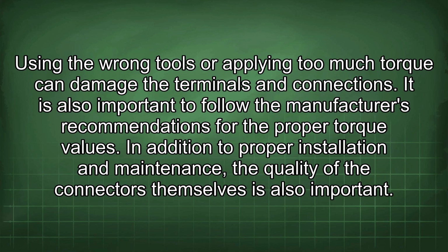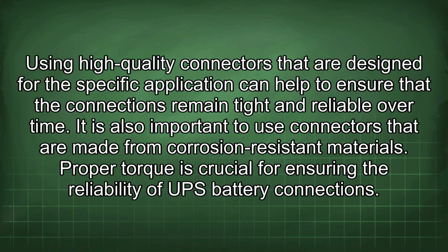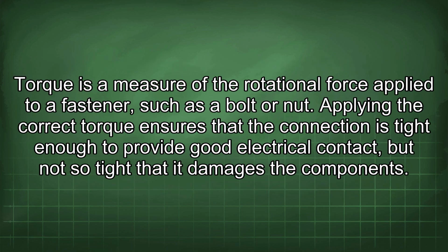In addition to proper installation and maintenance, the quality of the connectors themselves is also important. Using high-quality connectors that are designed for the specific application can help to ensure that the connections remain tight and reliable over time. It is also important to use connectors that are made from corrosion-resistant materials. Proper torque is crucial for ensuring the reliability of UPS battery connections. Torque is a measure of the rotational force applied to a fastener, such as a bolt or nut. Applying the correct torque ensures that the connection is tight enough to provide good electrical contact, but not so tight that it damages the components.